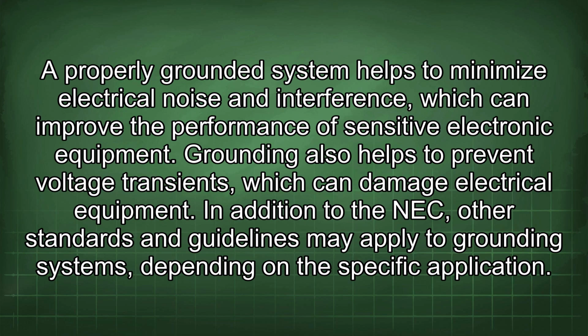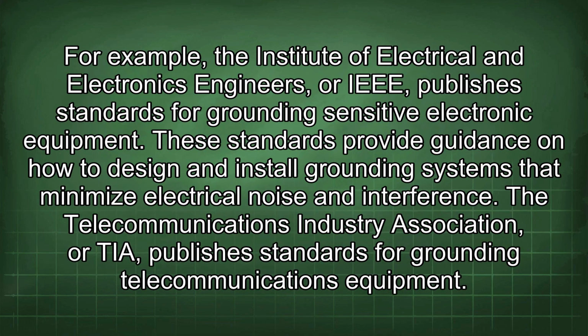Grounding also helps to prevent voltage transients, which can damage electrical equipment. In addition to the NEC, other standards and guidelines may apply to grounding systems depending on the specific application. For example, the Institute of Electrical and Electronics Engineers, or IEEE, publishes standards for grounding sensitive electronic equipment. These standards provide guidance on how to design and install grounding systems that minimize electrical noise and interference.